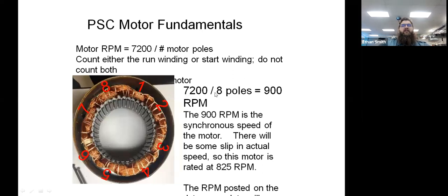So you take 7,200 and divide it by the number of poles. This particular one we're looking at has 8 poles, and that would equal a 900 RPM motor. So you take 7,200, which is the fastest motor you're going to get to run without any auxiliary controls on a single phase service at 60 hertz, and you divide that by 8, and that will give you your RPM output of that motor.